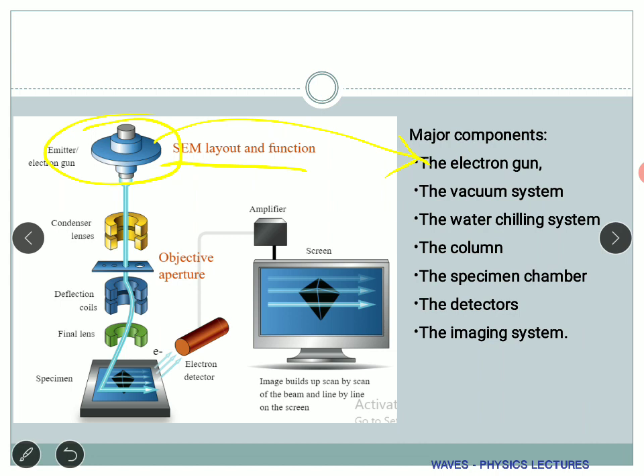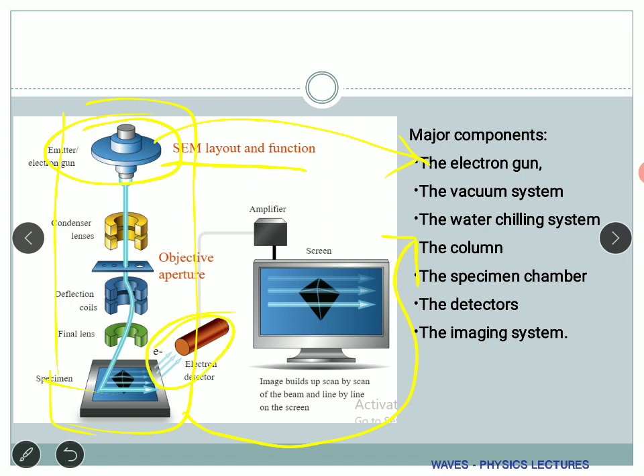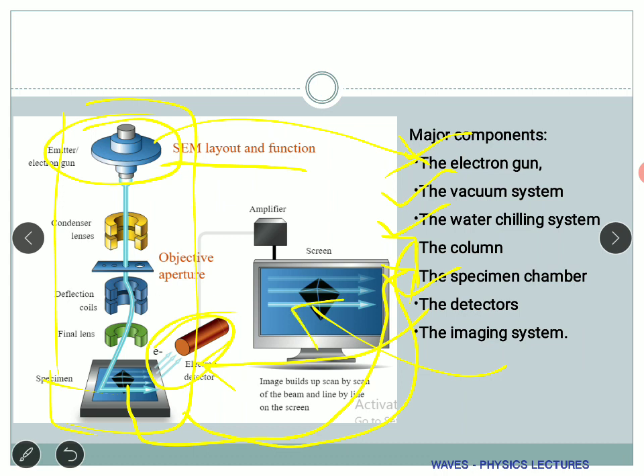We also have the vacuum system. This entire thing is put inside a column, and the space where the electron is generated or detected is placed in vacuum — there is a specific need for that. We have the water chilling system because it generates a lot of heat and we need to keep it cool. Then we have the specimen chamber where the specimen is kept, the detector, and finally the imaging system. This is a very simple layout of a scanning electron microscope.